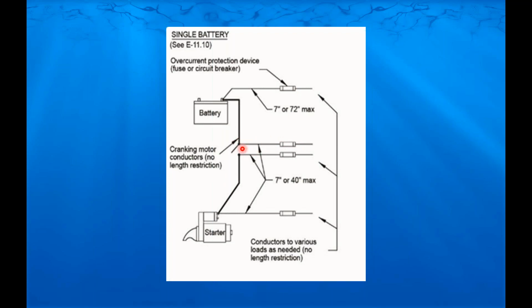And now this is on the unswitched side. You're going to be on the switch side, more than likely feeding your panel. You can use this as your source of power. Then you either have 7 or 40 inches to get your proper overcurrent protection in just for that auxiliary circuit, whatever it may be. In most cases, again, our intent is still to get that overcurrent protection as close to the battery as possible. In a case where you have a separate battery for your house loads, that's not an engine starting battery, we like to see that overcurrent protection before the switch.